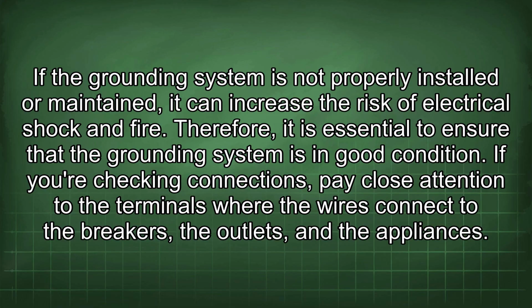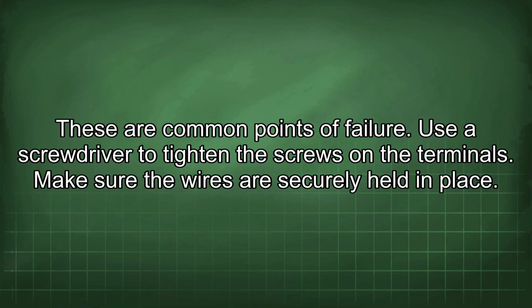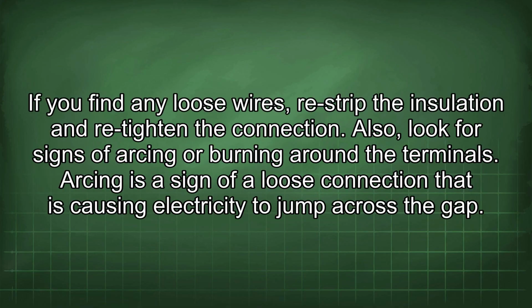If you're checking connections, pay close attention to the terminals where the wires connect to the breakers, the outlets, and the appliances. These are common points of failure. Use a screwdriver to tighten the screws on the terminals. Make sure the wires are securely held in place. If you find any loose wires, restrip the insulation and retighten the connection.